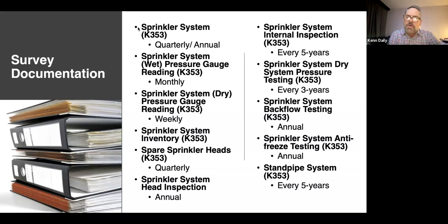And then from the floor, you have an annual inspection that you can do. This is probably the only thing on this slide that you can do yourself. You as maintenance can inspect every head in the building, by room, indicating that they're all clean, they're not corroded, they're not leaking, they're not damaged, they don't have any overspray, et cetera. They appear to be working and appear to be correct.